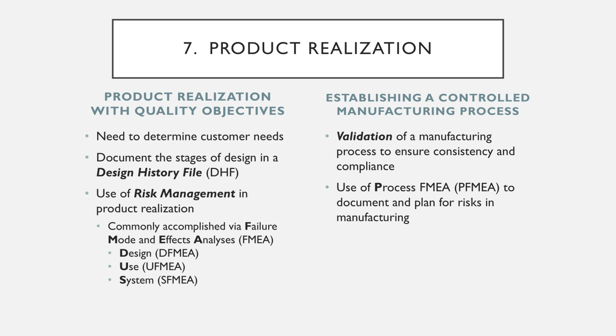So at the start of this brainstorming session, you might outline or list all the components, processes, or steps involved in the design, use, and manufacturing of a particular device. And again, some of those might be subdivided if you're only talking about the manufacturing process, the use of that device, or the design of that device. And you would brainstorm all possible ways that the device might fail. So in a use FMEA, you might say, well, what happens if the surgeon drops this on the floor in a surgical suite? What should they do in that case?